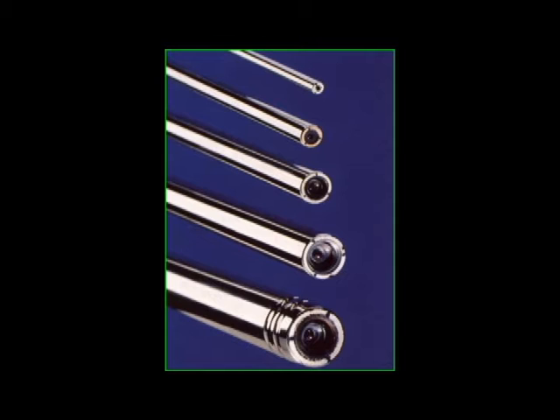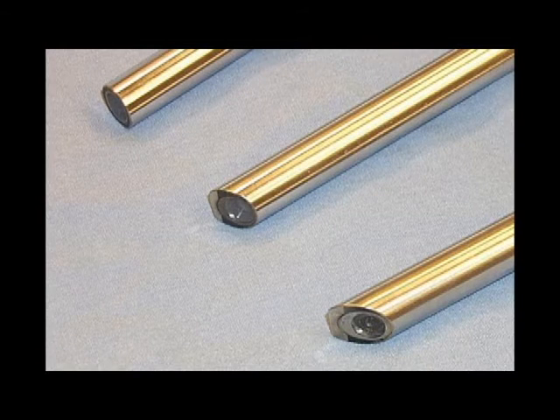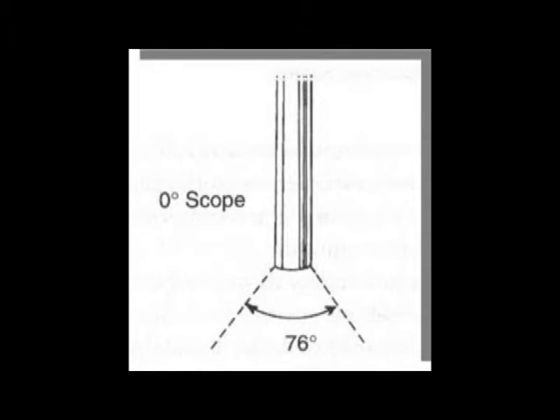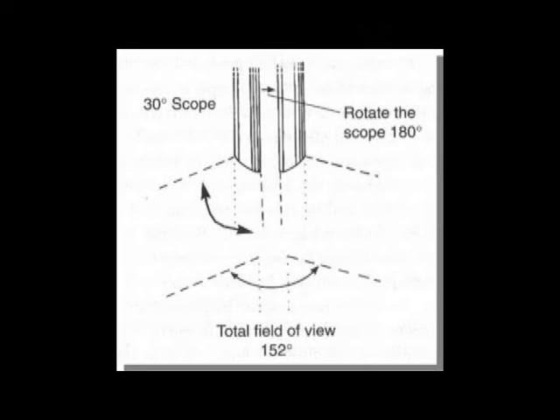Laparoscopically, when we're looking inside the abdomen, the scopes we use are usually either 10 or 5 millimeters in diameter. Looking at the very front of them — as I've shown you in class — they're either zero degree, meaning they look straight ahead, or 30 degree, meaning they have a declination of about 30 degrees downward. That allows us to look around corners to an extent. Generally, we utilize 30 or 45 degree scopes for abdominal procedures, and I try to do most of mine through a 5 millimeter scope, which leaves a much smaller incision.